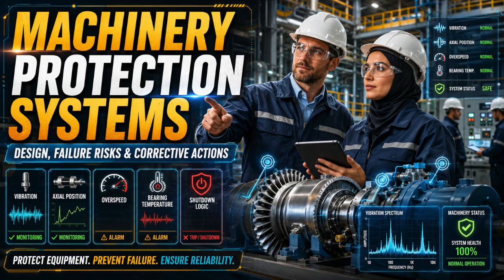Now, bearing temperature. Bearing temperature looks simple until you ask one serious question. Where is the sensor located? A temperature sensor does not measure the whole bearing. It measures the temperature where it is installed. If it is not near the load zone, if it is not properly embedded, if it does not have positive thermal contact, if it is placed away from the critical oil film region, then you may get a clean, stable, precise reading that tells you very little about actual bearing distress. That is a dangerous kind of precision.